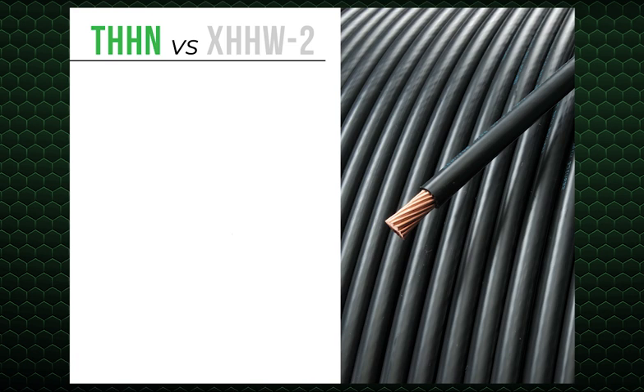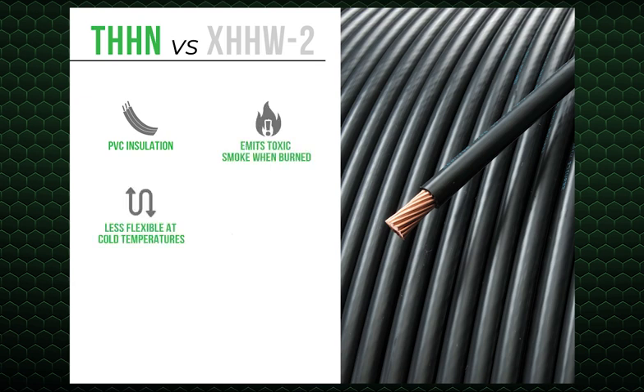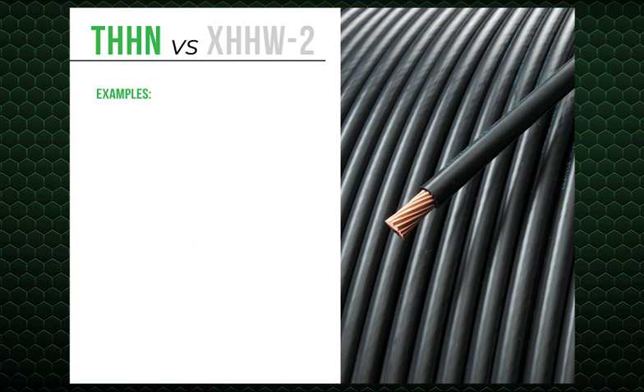THHN and THWN-2 are thermoplastic products. They use a PVC insulation, which can lead to current leakage and dielectric breakdown in demanding circuits or from chemical or environmental exposure. PVC emits a toxic smoke when burned and is less flexible at cold temperatures. It is lighter in weight and less expensive to manufacture. This process can typically be repeated by applying heat to remelt insulation. Some examples of thermoplastic compounds are polyvinyl chloride, PVC, polyethylene, PE, polypropylene, PPE.